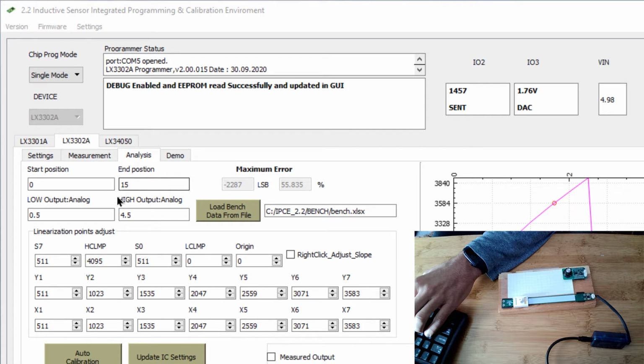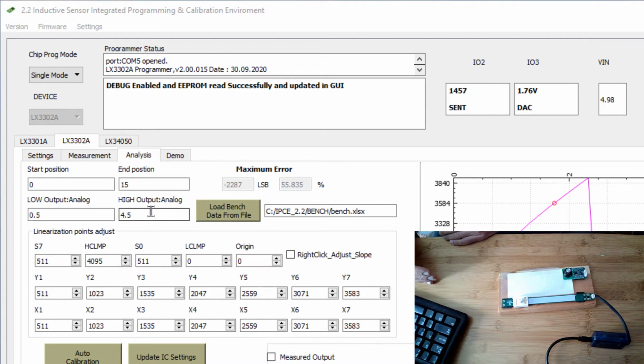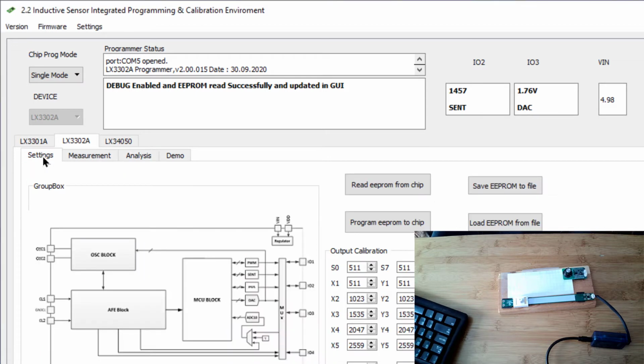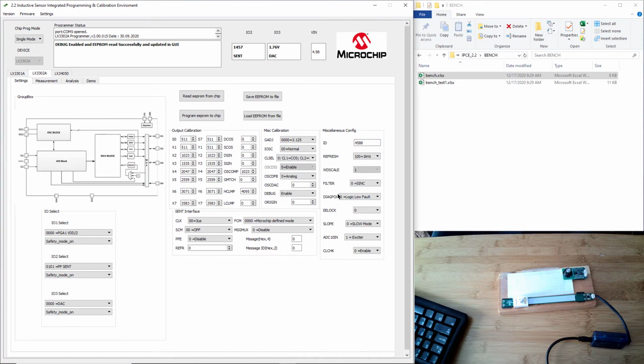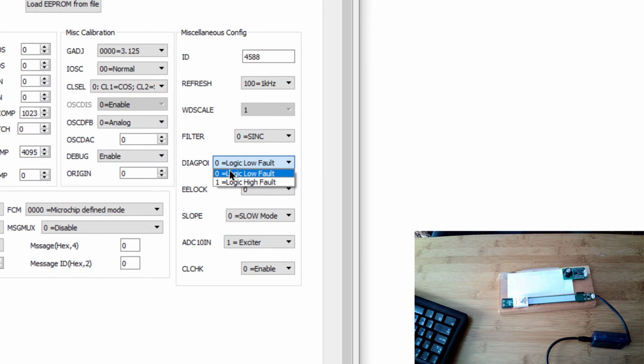and the last one is 15, and we're going to map that to 0.5 volts on the output and 4.5 volts on the output. Now we recommend that you don't go over the full measurement output value of 0 to 5, because we can then reserve these voltages below 0.5 volts and above 4.5 volts to indicate a fault. And our IC, if it detects a fault, will output, in this case, a 0, but you can also have it so that the IC will output 5 volts if there's a fault detected. And this is determined by this diagnostic polarity flag that's shown right here. Right now it's set up as logic level low for a fault.